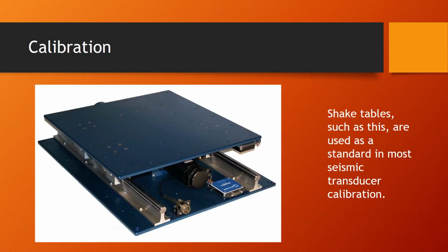This is a picture of the shake table. The seismic transducer would go on here, and the shake table would have a known movement, used as the standard to calibrate seismic transducers.